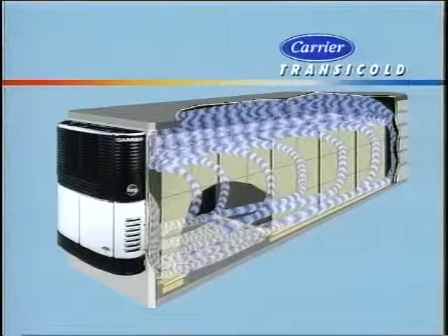Just a word of caution, anytime the start-stop light is on, the unit is programmed to start automatically without any help from you. Our unit is now running the auto start-stop mode. This means that the unit will run until box temperature is the same as the set point. Once box temperature and set point are the same, the unit will cycle off and remain off until it is needed once again to bring box temperature back to set point.